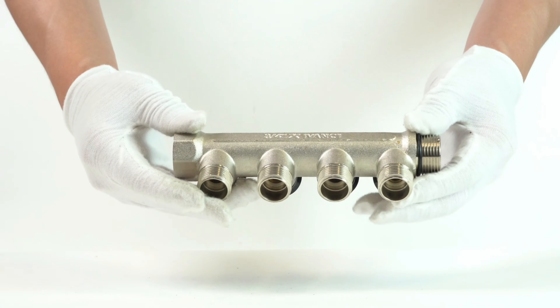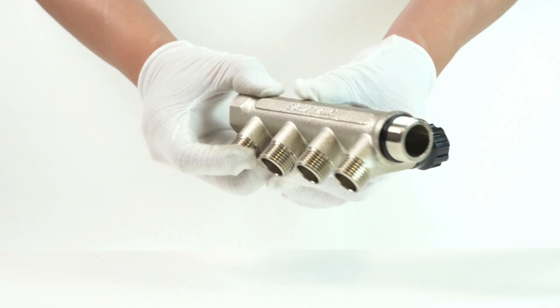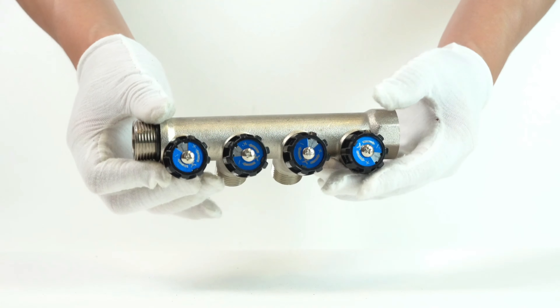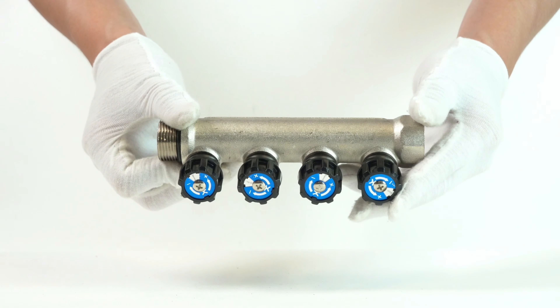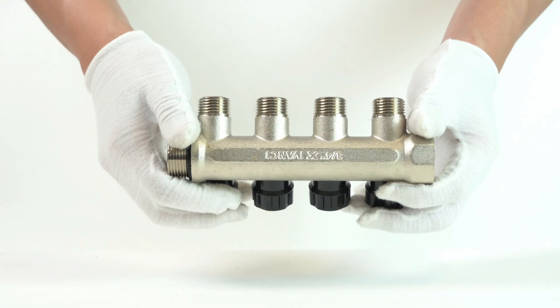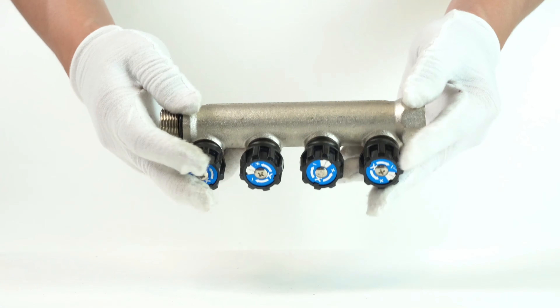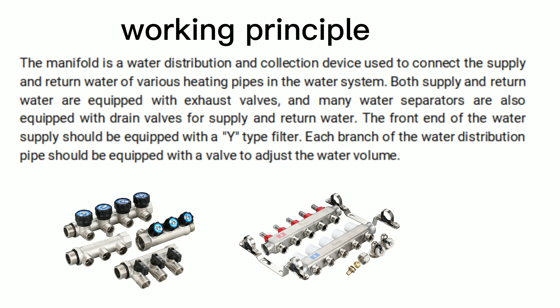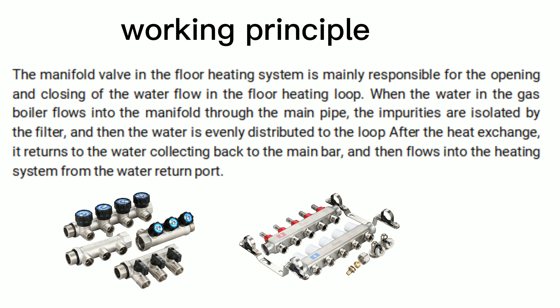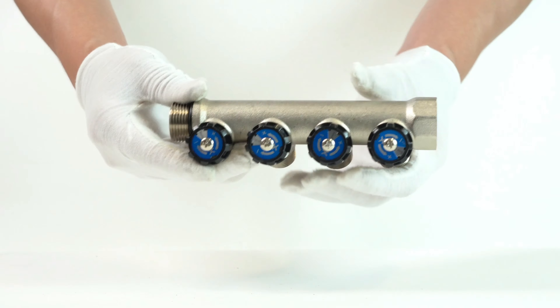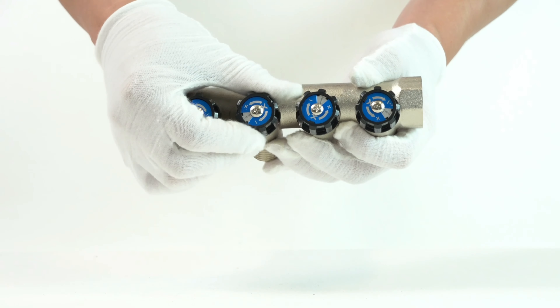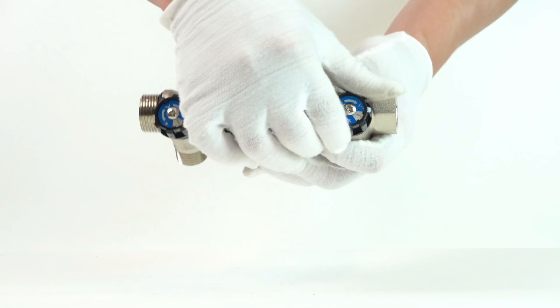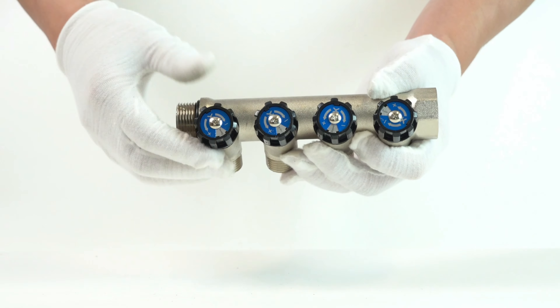Both supply and return water are equipped with exhaust valves, and many water separators are also equipped with drain valves for supply and return water. The front end of the water supply should be equipped with a Y-type filter. Each branch of the water distribution pipe should be equipped with a valve to adjust the water volume.